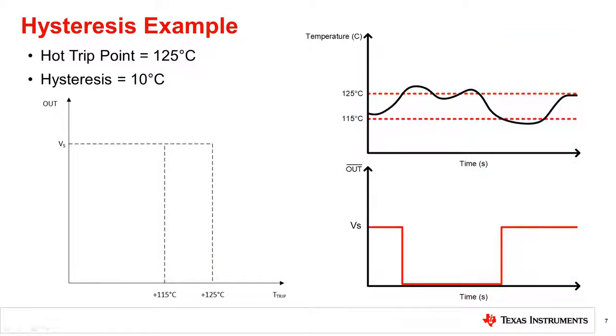Now consider a trip accuracy of plus or minus 0.2 degrees Celsius. In the worst case scenario, the temperature is sensed at 124.9 degrees Celsius, and the output will not trip. With the trip accuracy of plus or minus 0.2 degrees Celsius, the next sample shall yield 125.1 degrees Celsius, which will cause the output to trip.